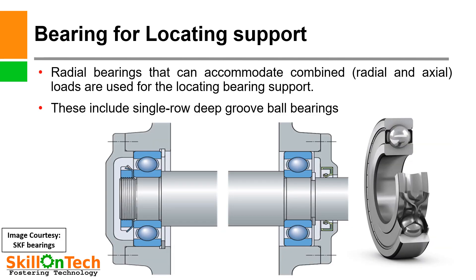Bearing for locating support. The bearing in the locating position, which is typically positioned at the drive end of a machine, supports the shaft radially and locates it axially in both directions. It must therefore be fixed in position both on the shaft and in the housing. Suitable bearing types for locating support include deep groove ball bearings, which accommodate both radial and axial loads.